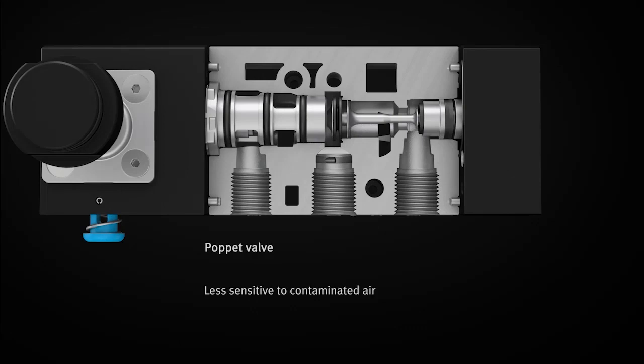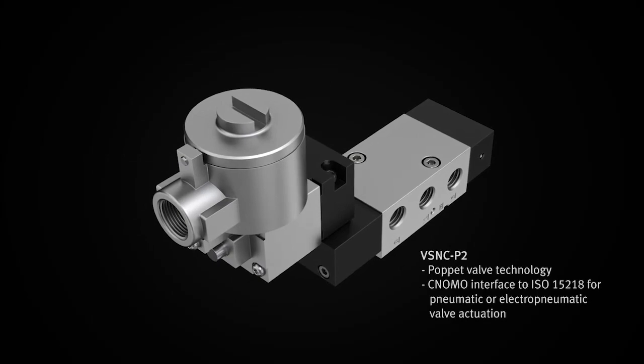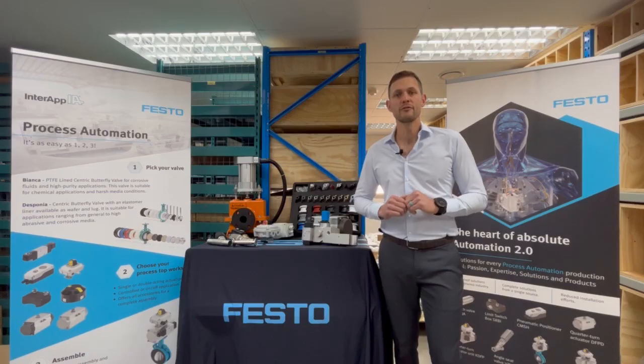The poppet valve design VSNC-P2 really comes into its own when the demands of the application increase. It offers better tolerance against contaminated pneumatic air, less leakage and fewer dynamic seals, which can have a positive effect on the service life.